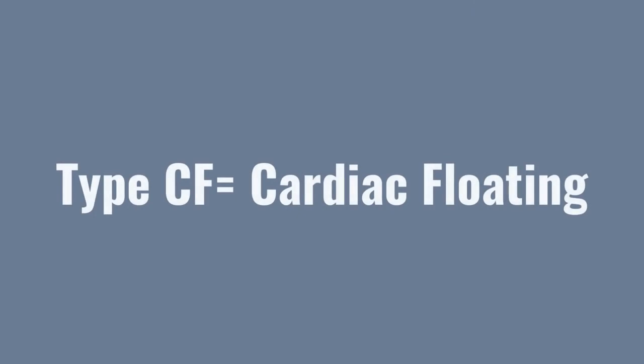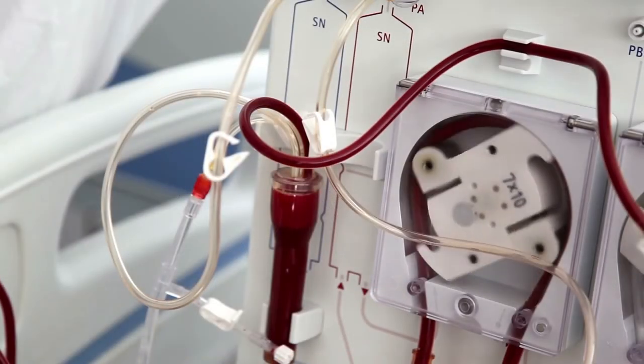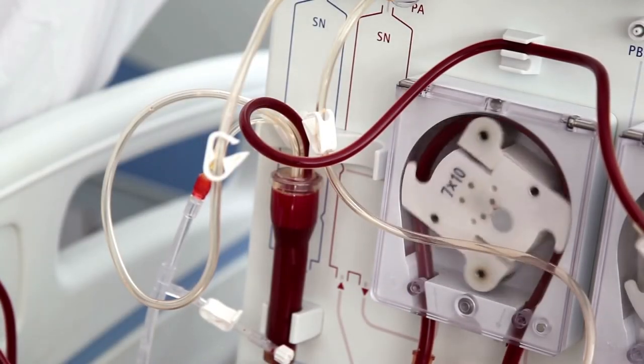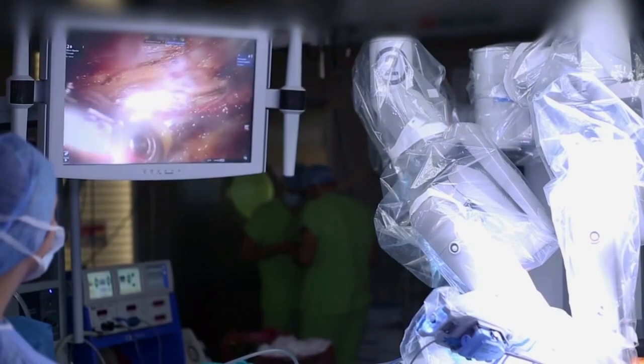Type CF: Cardiac floating requirements are the strictest of the applied part classifications, allowing only up to 10 microamps of patient leakage. Any part that comes into contact with the heart or bloodstream is classified as CF. Examples of type CF include dialysis, LVAD or artificial heart, and surgical equipment. Since the risk of physical harm is greatest when applied parts contact the heart or bloodstream, the limits are considerably lower for type CF.